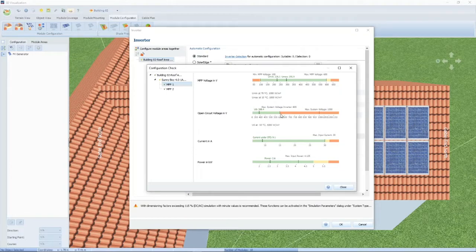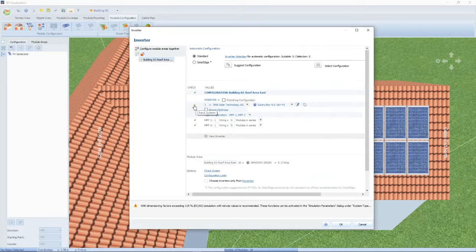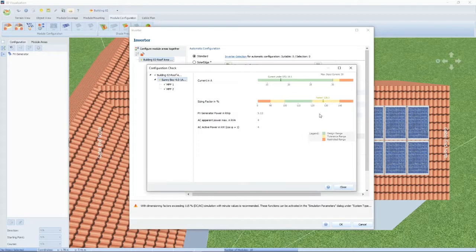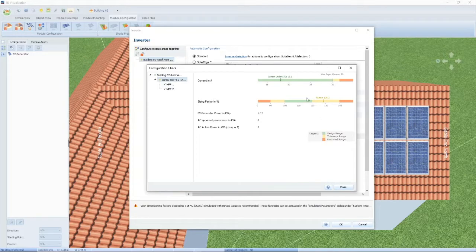You'll also see a yellow check mark next to the inverter. The yellow check mark tells us that the design factor is 128%, meaning the inverter is a little bit undersized for the PV modules — but it's still within a tolerance range and is normally acceptable. Most inverters will allow up to a 150% factor.